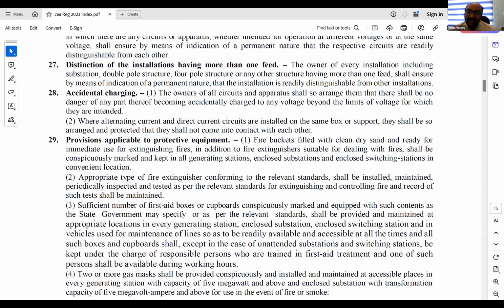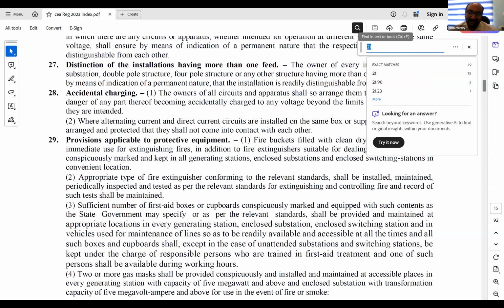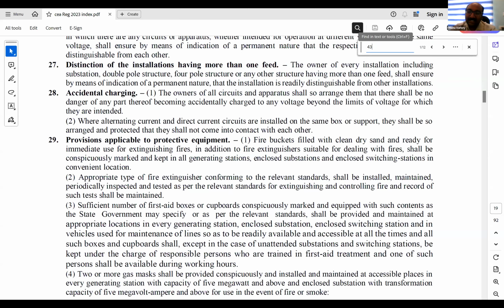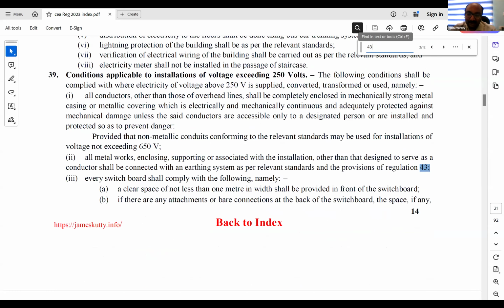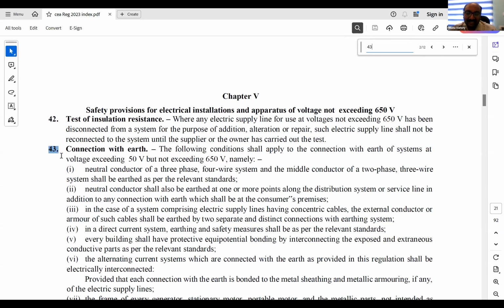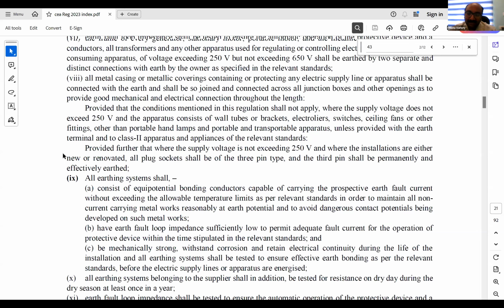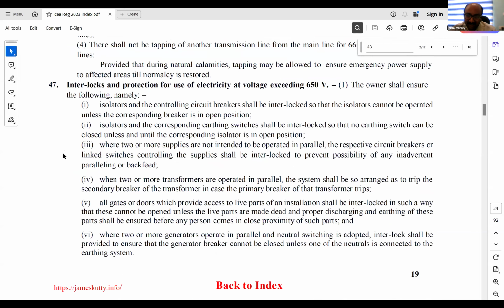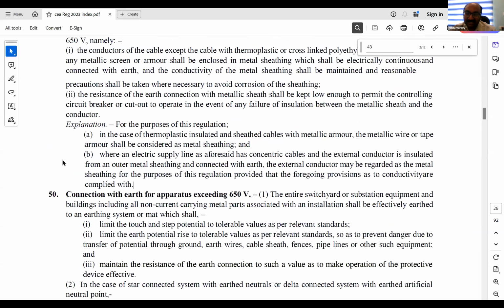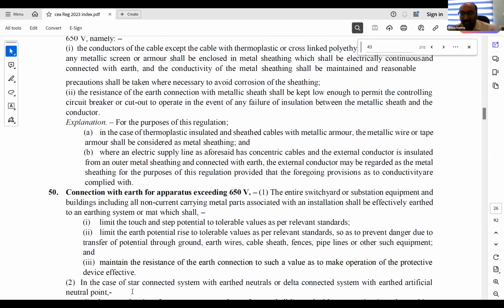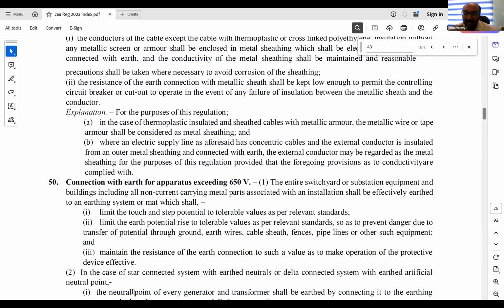Yes, sir. Actually, regarding the earthing of installations, you have to see HT and LT installations separately, because the methods of protection that are employed in these two installations use two different philosophies. Regarding the HT side, that is given in Regulation 50 of the CEA regulations. The protection is provided by the current that is returned by the earth electrode. So the integrity of the earth electrodes is important in case of an HT installation.